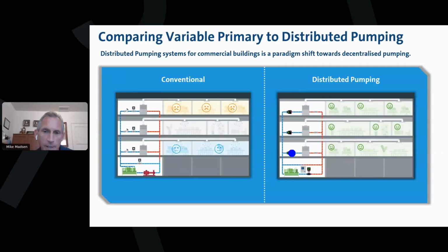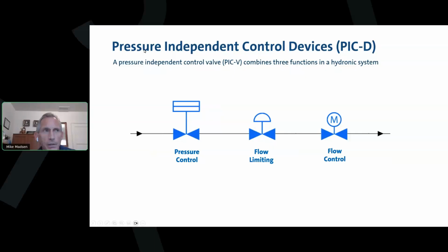So one way to think about that is we'll size these pumps just like we do most pumps, for when all the system is running and all the air handlers are requiring flow. But if this middle air handler and the top air handler are not running, this pump only needs to supply enough chilled water to pull from the decoupler and push through its coil. When this air handler comes on, this pump will speed up a little bit with its built-in VFD and just produce flow to pull from the decoupler and push through its coil. So it's always self-balancing.